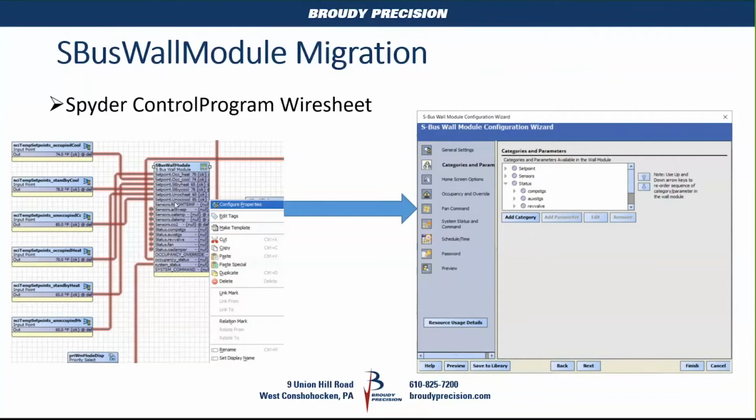And then you link other components to that. So here I'm representing, if you look, status compressor stages. You'll see down here you got status compressor stages. So you link directly to this object, and then underneath this object you have a configuration screen that you go to configure all of the points that you want to display on there.